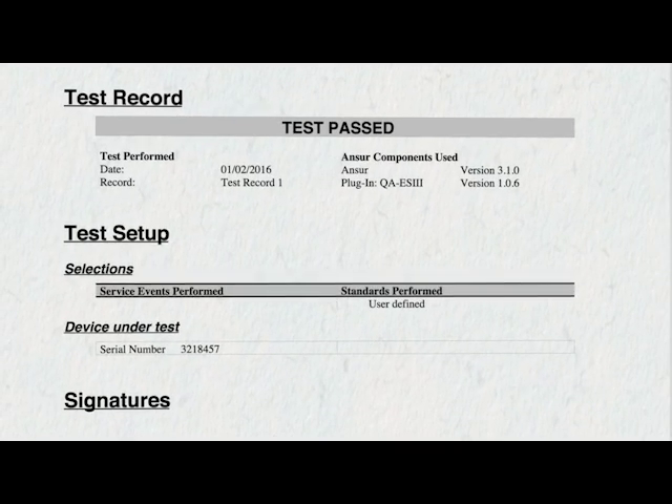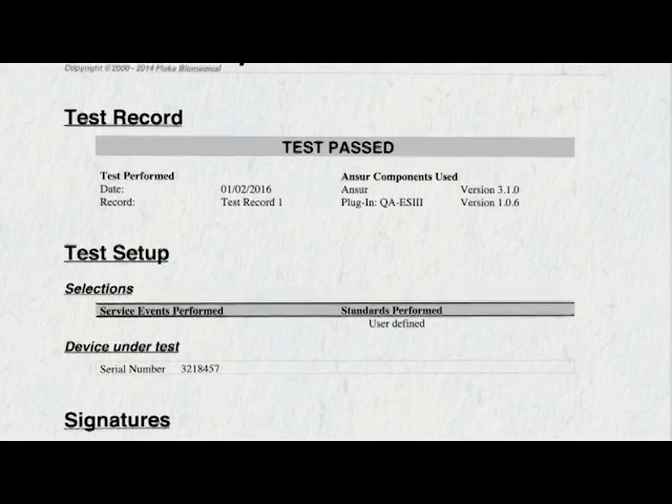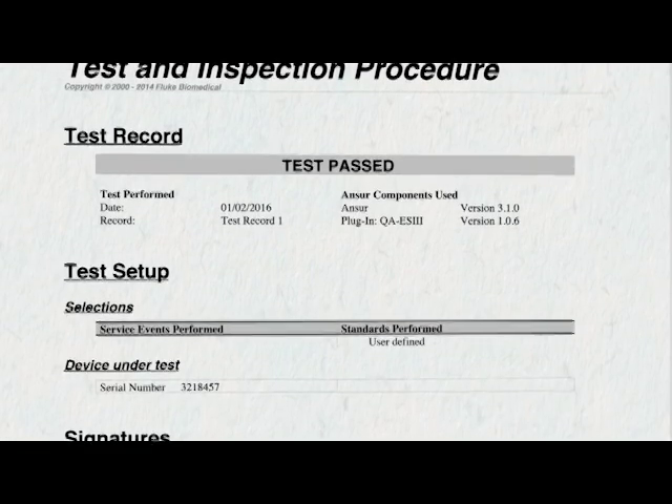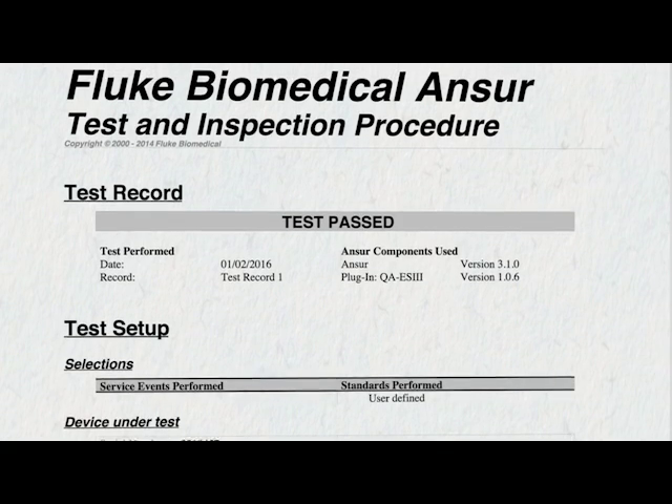Ansur software can produce a single electronic test report which displays all preventative maintenance tasks, including visual inspection, electrical safety, and performance characteristics.